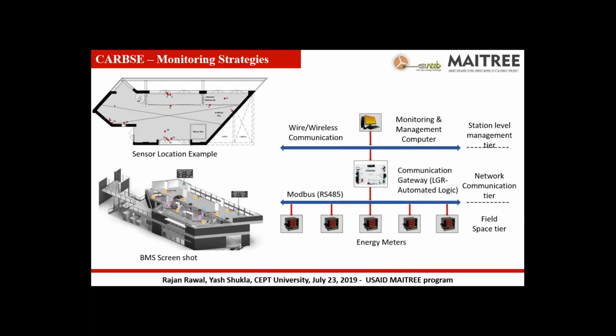We also looked at the three tiers of the building management system. First is the field space. The energy meters provide us the information of what's happening at a component level, and then we integrate into a network communication tier where the information from the field sensors or field devices is integrated into one centralized system. And then we have several wired devices as well as wireless devices, which help us cover a diverse set of measurements in the building.